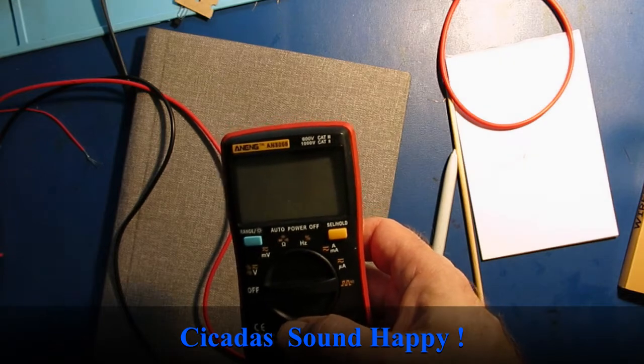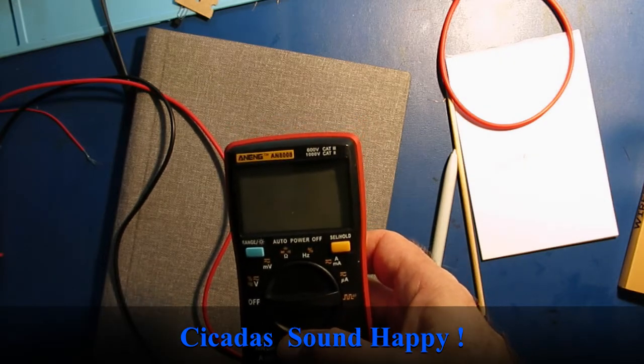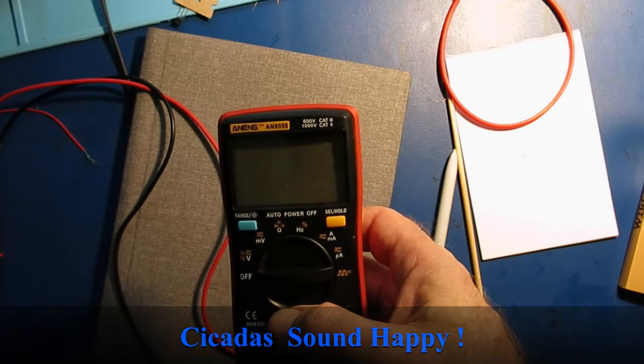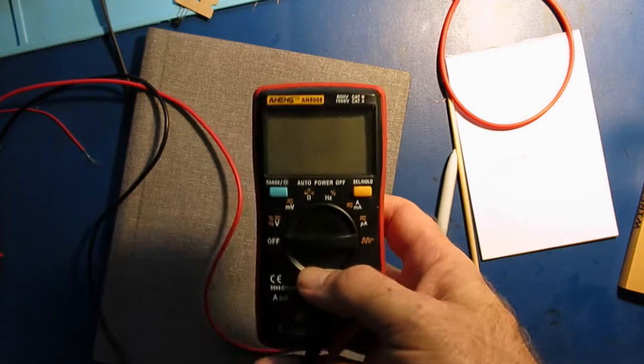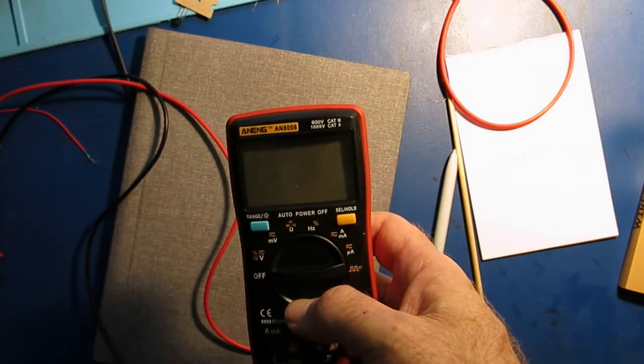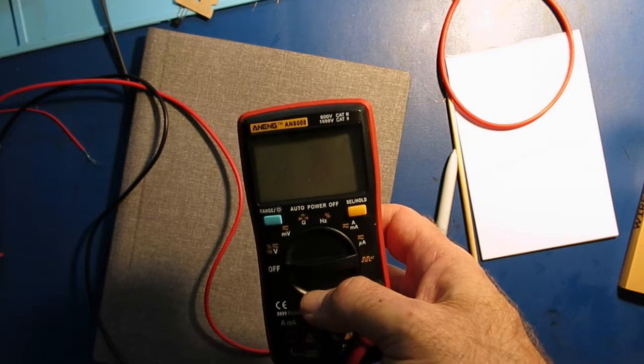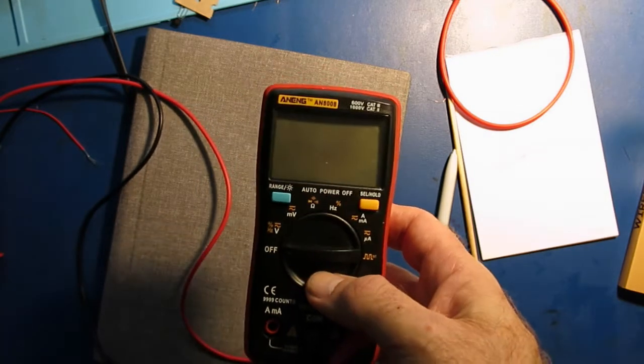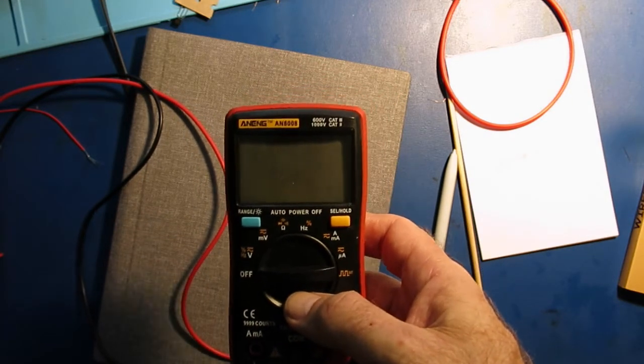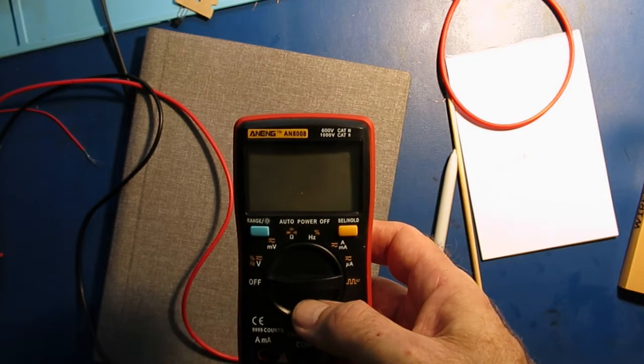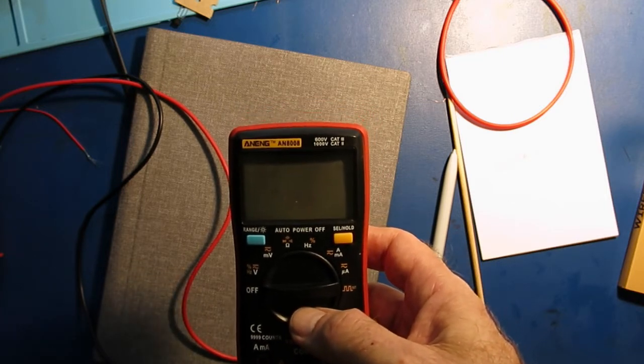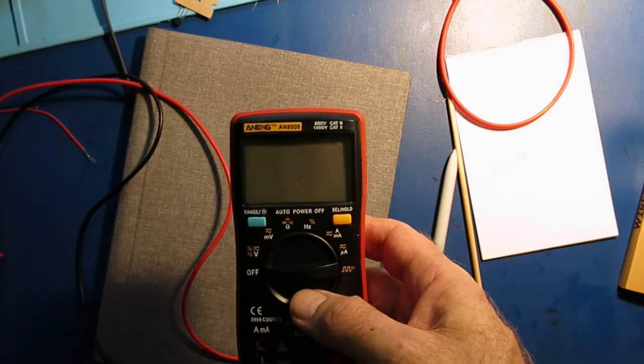Well, if you're fortunate enough to have access to a known length of cable, the same type that you're using your multimeter to try to estimate the length of, then you could take your multimeter and measure the capacitance on that known length and come up with a capacitance per foot number to use in your calculations.